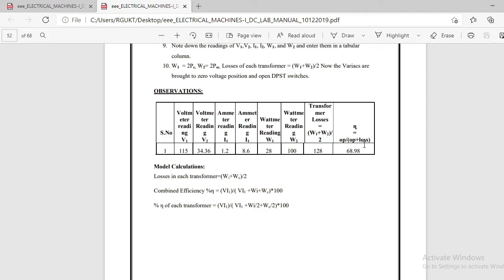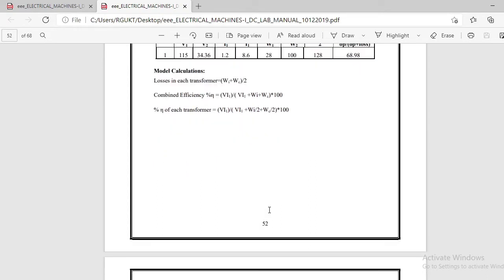So to find the efficiency, the formula is output divided by output plus losses. Already you know the losses. Output is nothing but V into I1. If you want to find the combined percentage efficiency, the formula is V I1 divided by V I1 plus iron losses plus copper losses, into 100. Losses in each transformer are the sum divided by 2. Next, for an individual transformer, it is V I1 divided by V I1 plus W_I by 2 plus W_C by 2. Clear? In this way, in this experiment, we find the combined efficiency of the transformers, or else the efficiency of each transformer. So this is about the Sumpner test. Thank you.